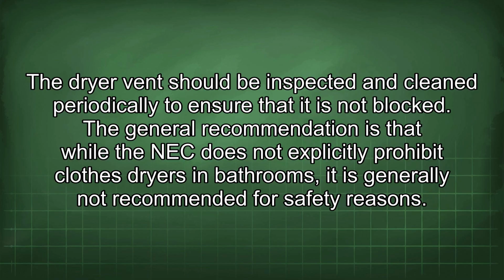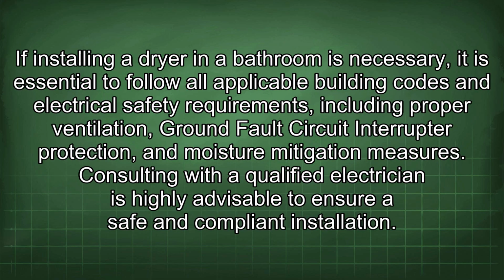The general recommendation is that while the NEC does not explicitly prohibit clothes dryers in bathrooms, it is generally not recommended for safety reasons. If installing a dryer in a bathroom is necessary, it is essential to follow all applicable building codes and electrical safety requirements, including proper ventilation, ground fault circuit interrupter protection, and moisture mitigation measures. Consulting with a qualified electrician is highly advisable to ensure a safe and compliant installation.